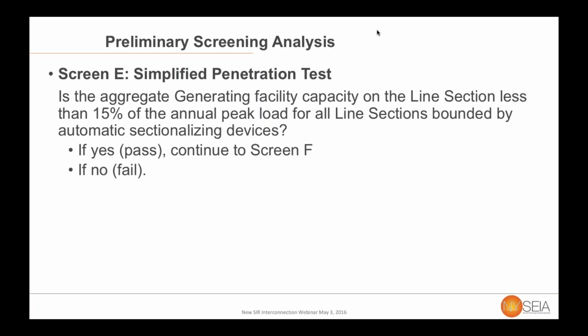Screen E is likely to be the most significant of those preliminary results, preliminary analysis screens. It's the most likely screen to fail, and it's the most likely screen to interest you in looking at supplemental review. So this simplified penetration test says, is the aggregate DG, so your facility plus all of the existing plus the queued ahead of you, does that exceed 15% of the peak load on the circuit or the section of the circuit that is segmented by these automatic sectionalizing devices?